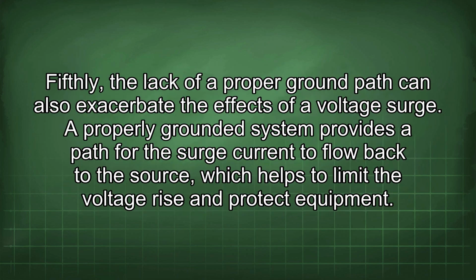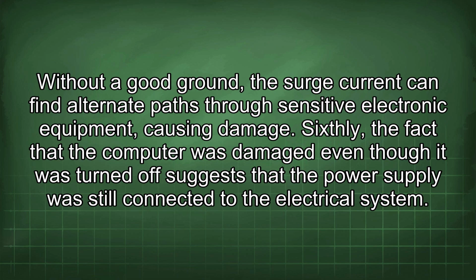Fifthly, the lack of a proper ground path can also exacerbate the effects of a voltage surge. A properly grounded system provides a path for the surge current to flow back to the source, which helps to limit the voltage rise and protect equipment. Without a good ground, the surge current can find alternate paths through sensitive electronic equipment, causing damage.